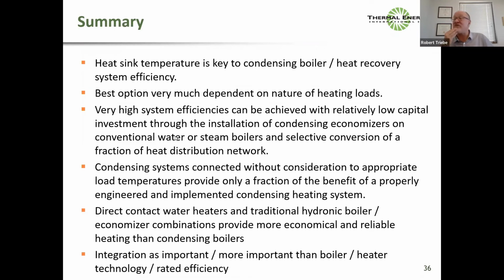Condensing systems without consideration to appropriate load temperatures provide only a fraction of the benefit that they can. Direct contact water heaters and traditional hydronic boiler economizer combinations are a more economical and reliable option than condensing boilers. And integration is as important or more important than the boiler or heater technology or rated efficiency.